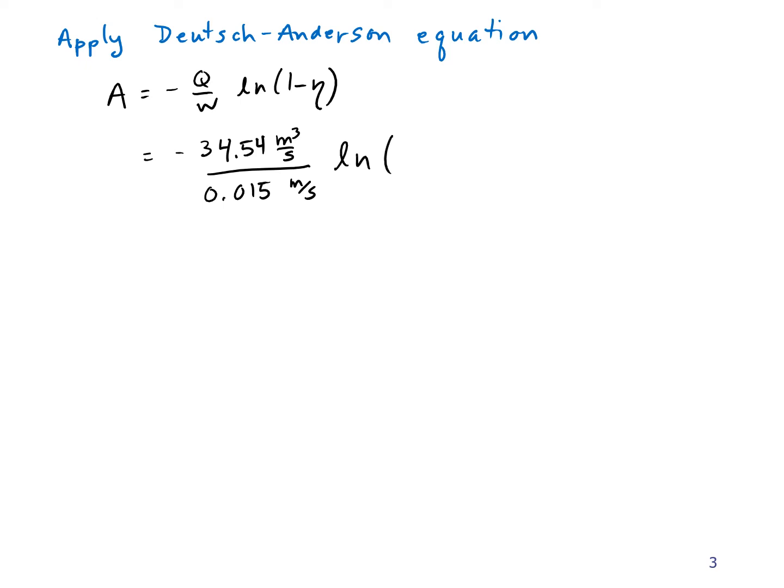So that's times the natural log of 1 minus the efficiency. We're seeking an efficiency of 99%, so I substitute that in. And when I solve for this, I get 10,600 square meters. So that's the total area, and if each of my plates is, let's say, 1,000 square meters, I would need at least 10 of them, so I'd need 11 of them.